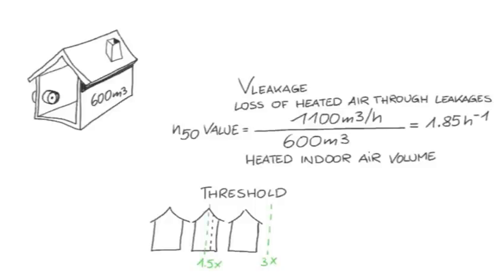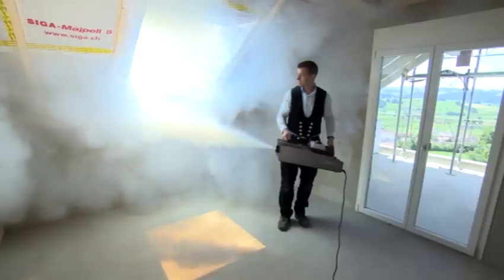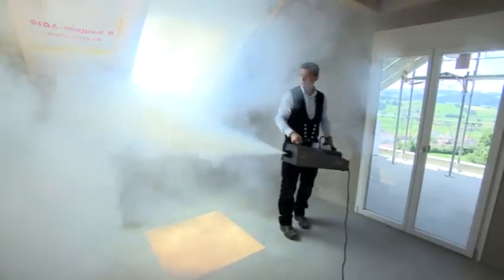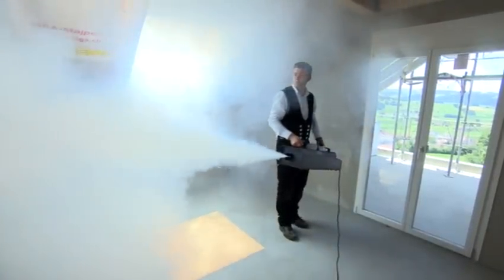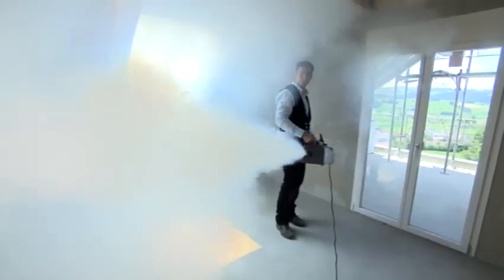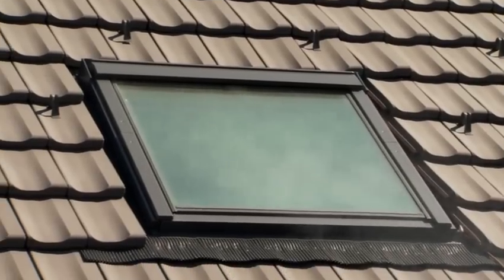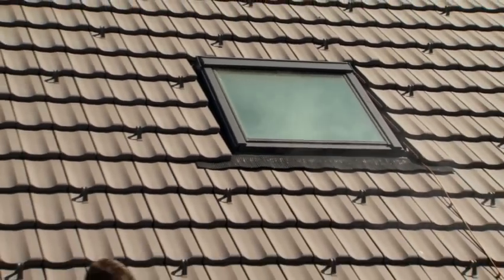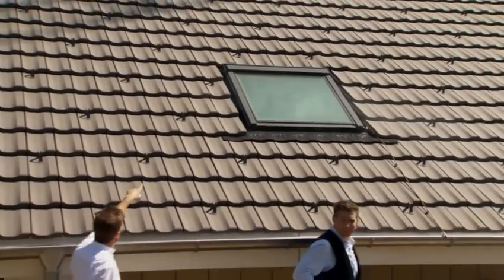In our example, the air change rate is too high because the architect planned a building with a ventilation system. The permissible limit value of 1.5 has been slightly exceeded. The craftsman has to search for the leaks. To do so, he fills the entire structure with theatrical smoke. A positive pressure is established. It is now possible to see from the outside where smoke is escaping through the building envelope.